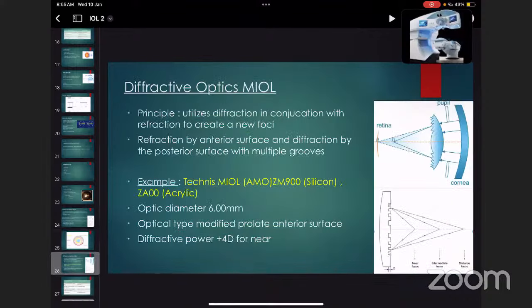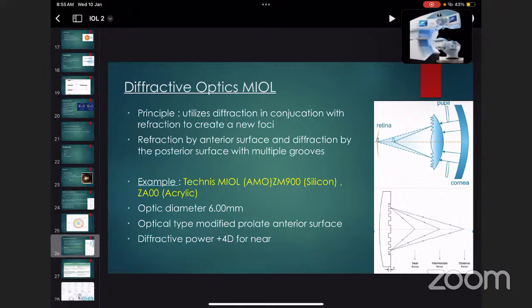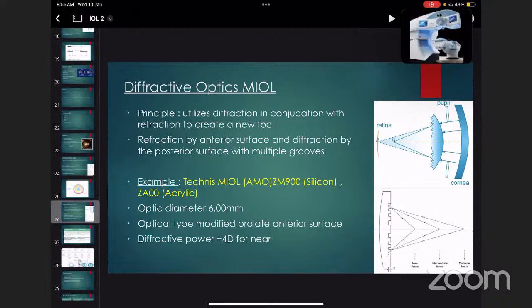Diffractive optics of multifocal IOL: principle is it utilizes diffraction in conjugation with refraction to create new foci. It causes refraction by the anterior surface and diffraction by the posterior surface with multiple grooves. Examples are Tecnis multifocal IOL ZM900, silicone-based IOL, and ZA9003, acrylic-based IOL, with optic diameter 6 mm and diffractive power for near plus 4 diopter.